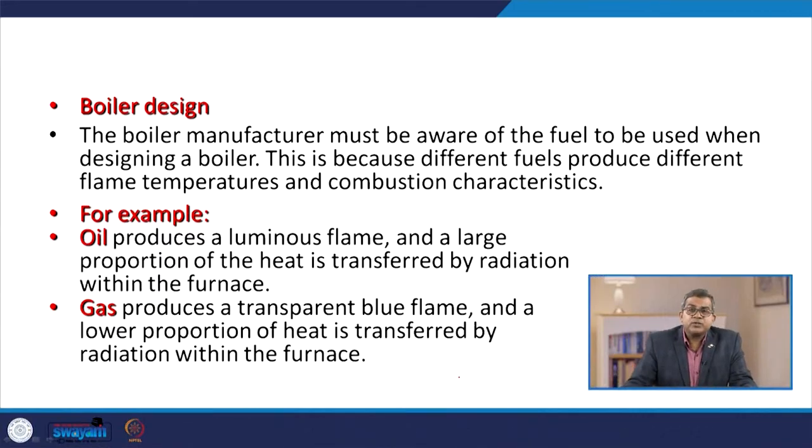Now, while considering the boiler design, the boiler manufacturer must be aware of what kind of fuel is to be used when designing the boiler. This is because a different fuel produces a different flame temperature and combustion characteristics. For example, oil produces a luminous flame, and a large proportion of the heat is transferred by radiation within the furnace. Gas produces a transparent blue flame, and a lower proportion of heat is transferred by radiation within the furnace.